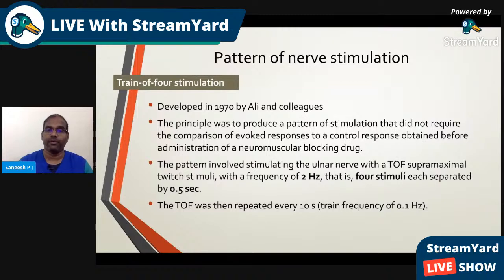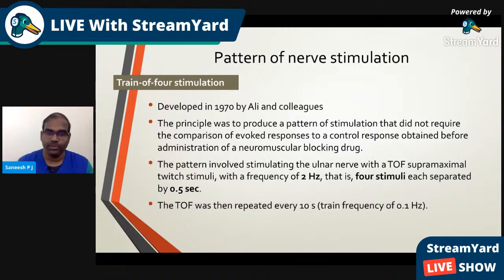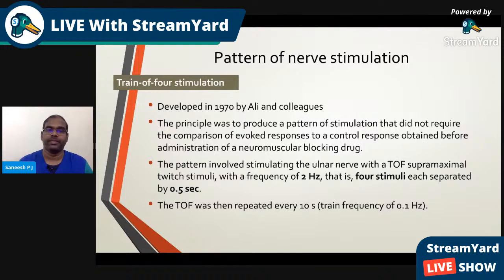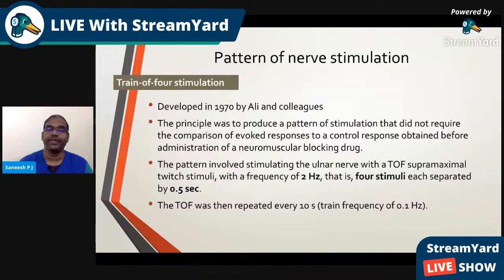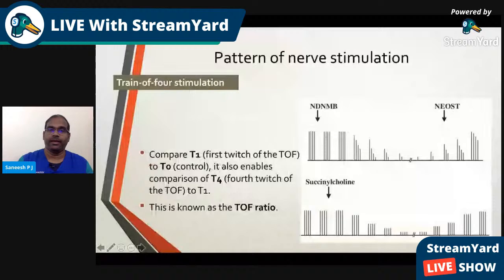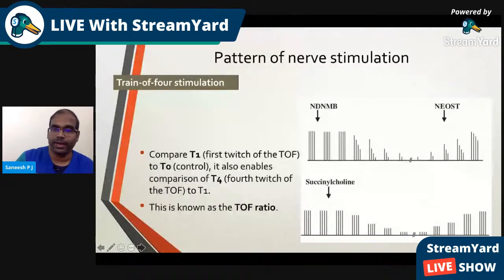The pattern involves stimulating the ulnar nerve with a train-of-four supra-maximal twitch stimuli at a frequency of two hertz — that is, four stimuli each separated by 0.5 seconds. The TOF is then repeated every 10 seconds, giving a train frequency of 0.1 hertz. This is the pattern we get with non-depolarizing neuromuscular blockade.